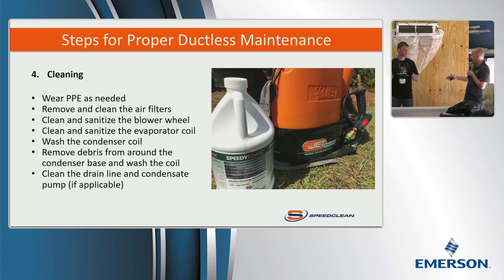You do not want to create damage to that evaporator coil, because in a lot of these coils that copper is super thin—I mean, super thin. If you've seen ductless units, we've seen plenty that start to get attacked due to chemicals, even in the air, and formicary corrosion will form right in the center of these coils. When I first started seeing it, I didn't believe it—I thought there was something in the manufacturing process—but you actually strip the fins away and you'll see there's a little formic leak right in the center.